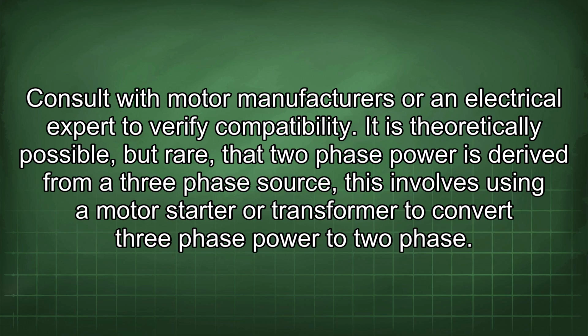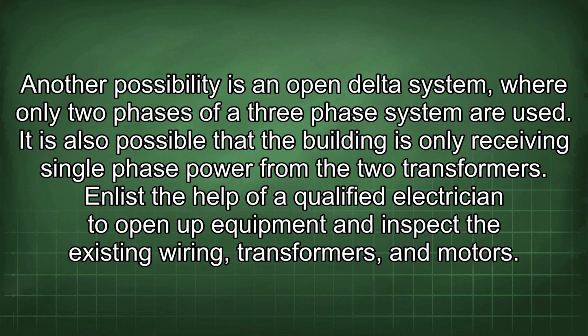It is theoretically possible, but rare, that 2-phase power is derived from a 3-phase source. This involves using a motor starter or transformer to convert 3-phase power to 2-phase. Another possibility is an open delta system, where only 2 phases of a 3-phase system are used. It is also possible that the building is only receiving single-phase power from the 2 transformers.